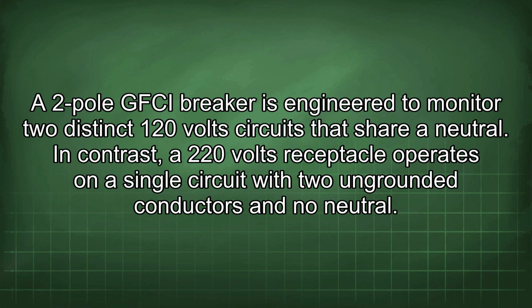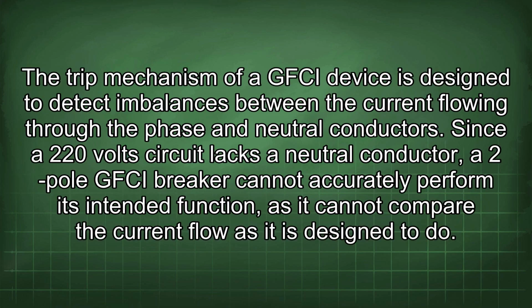A 2-pole GFCI breaker is engineered to monitor two distinct 120 volt circuits that share a neutral. In contrast, a 220 volts receptacle operates on a single circuit with two ungrounded conductors and no neutral. The trip mechanism of a GFCI device is designed to detect imbalances between the current flowing through the phase and neutral conductors. Since a 220 volts circuit lacks a neutral conductor, a 2-pole GFCI breaker cannot accurately perform its intended function, as it cannot compare the current flow as it is designed to do.